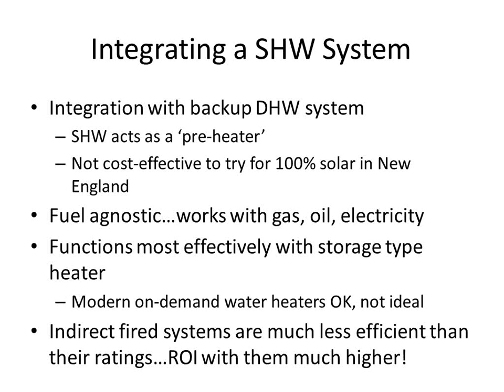And in fact, you may well be creating overheated water. You're going to start blowing pressure leaks out. So before you retrofit a system, it won't be a factor in a passive home. But if you're involved in a solar hot water installation and you've got an older tankless boiler, you've really got to do your homework and make sure that it's got a temperature sensor in it so that it will not fire if it's seeing hot water being delivered to it.